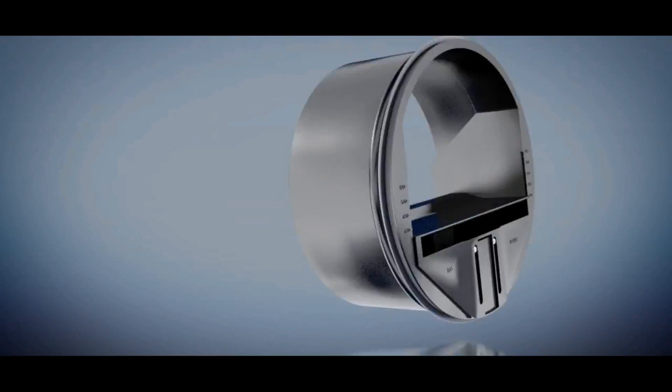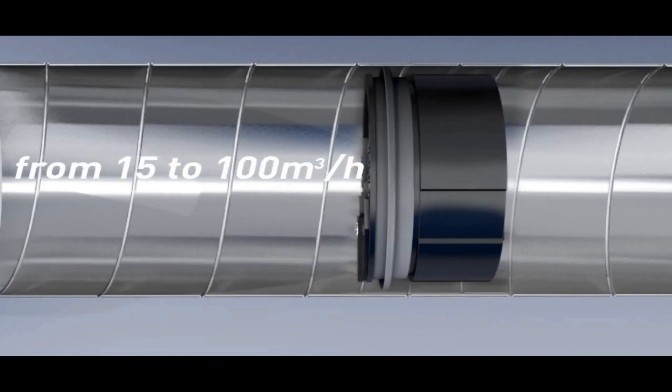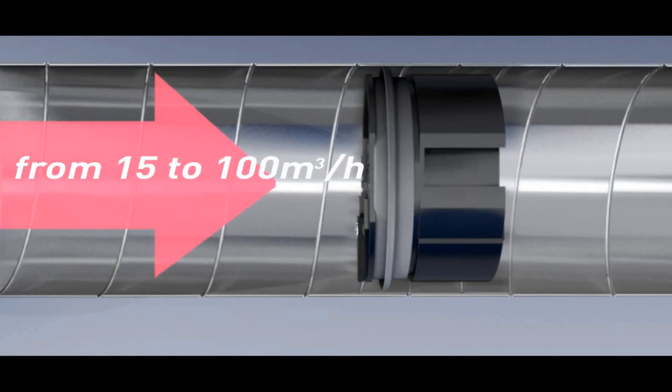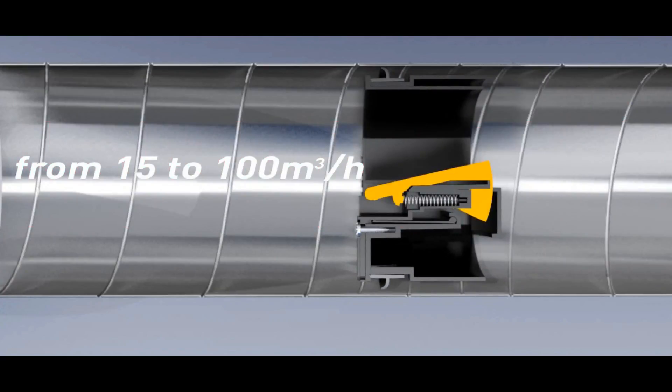For flow rates from 15 to 100 cubic meter per hour, the control flap is in the same direction of the air flow. As pressure increases, the rear of the flap lifts more or less to reduce the air flow.